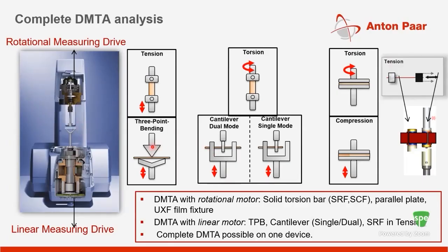So things like bending, compression, all the measurements which typically you do on a DMA type device, like 3-point bending, cantilever, all those are now possible when you put a linear drive. And one thing to point out here is the stroke length or the displacement possible with a device like this is almost 9,000 microns.